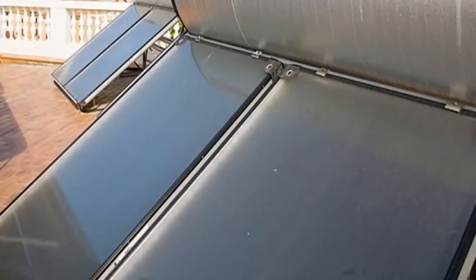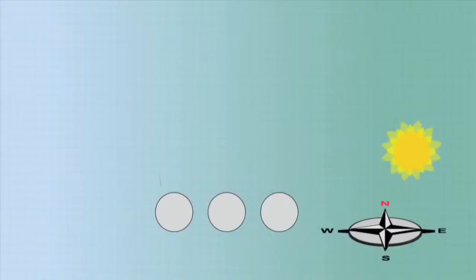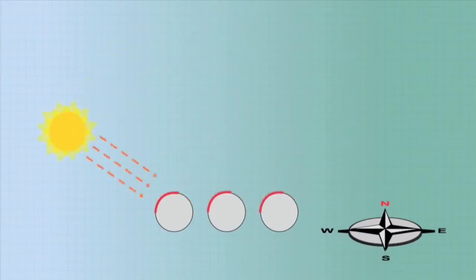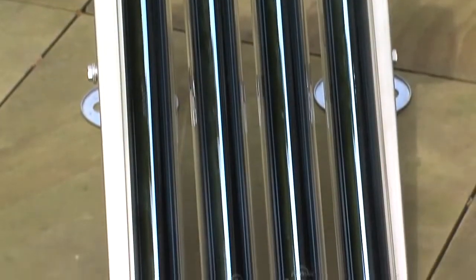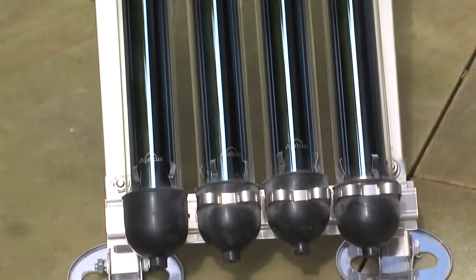There are two collector types to choose from, flat plate and evacuated tubes. Evacuated tubes have the advantage of receiving perpendicular radiation for a greater part of the day. This, combined with their vacuum insulation, means good winter performance.